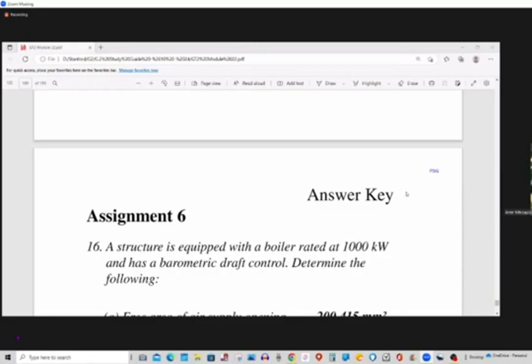When the air supply is provided by natural airflow from the outdoors for an appliance and a venting system with a draft control device is installed in the same space or enclosure, there shall be a permanent air supply opening having a cross-sectional area of not less than 1 square inch per 7,000 BTU per hour, or 310 square millimeters per kilowatt up to and including 300 kilowatt.